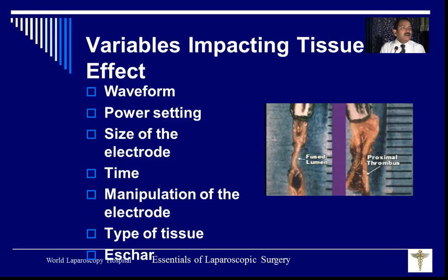And if you want to cut a bone, you cannot cut it with simple current, because in bone water content is very less. And if it is fat you want to cut, you can cut with very less wattage. So water content and type of tissue is important. Another variable is eschar formation. After 2, 3, 4, 5 minutes, the burnt tissue gets deposited over the margins of your instrument, in between the jaw. That creates like an insulation, and that will affect your effect.